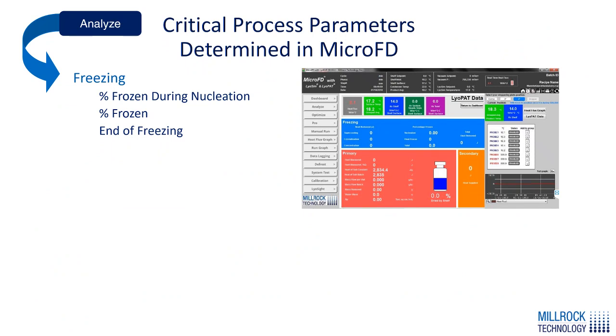Things that you can see using this technology that you can't see in other systems: we can tell you how much the product is frozen, how much is frozen during nucleation. We can see the end of freezing — essentially when the product has become stable and you can move on to primary drying. So no longer do you have to wait for a time-based event.